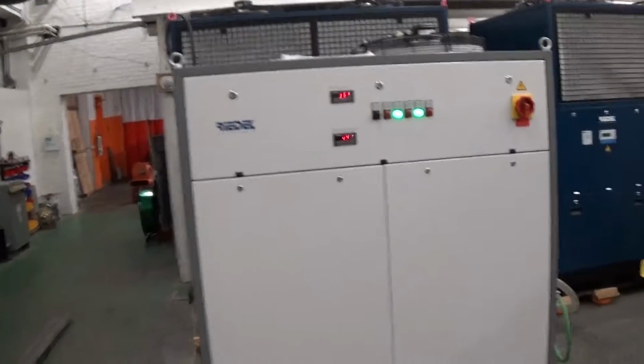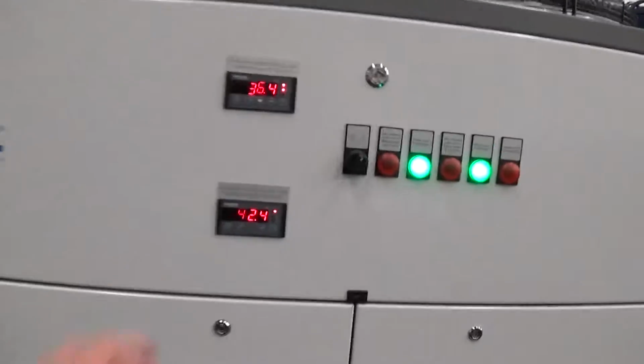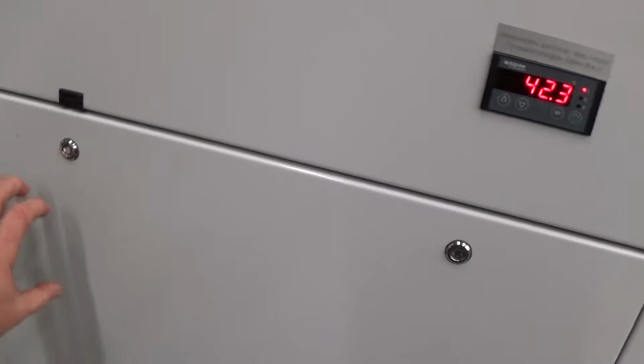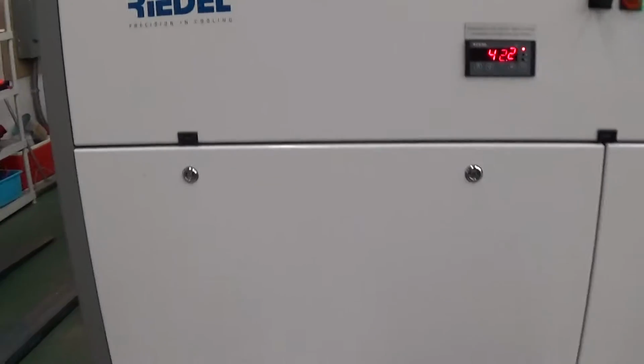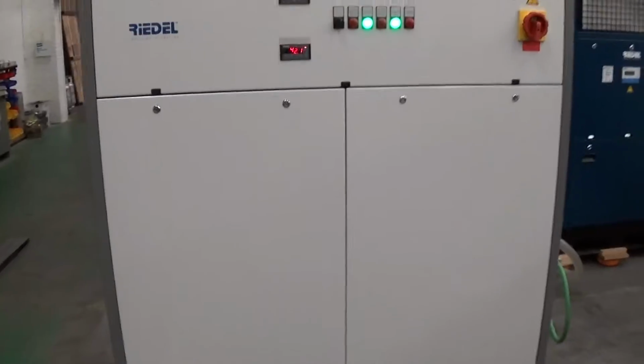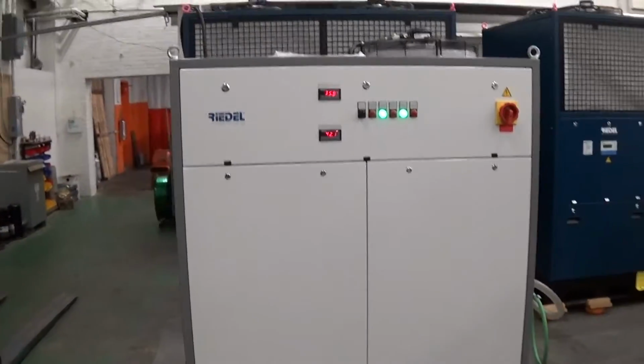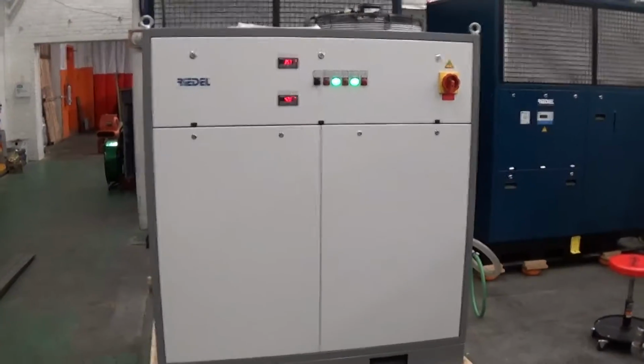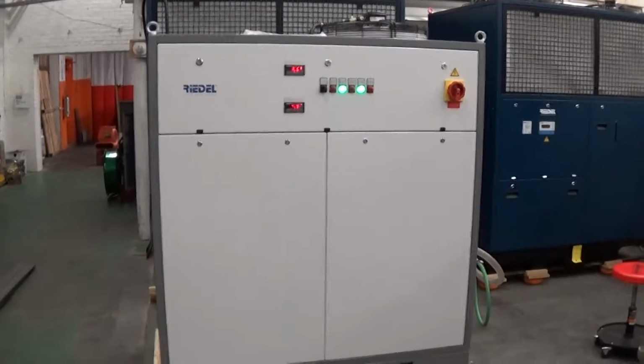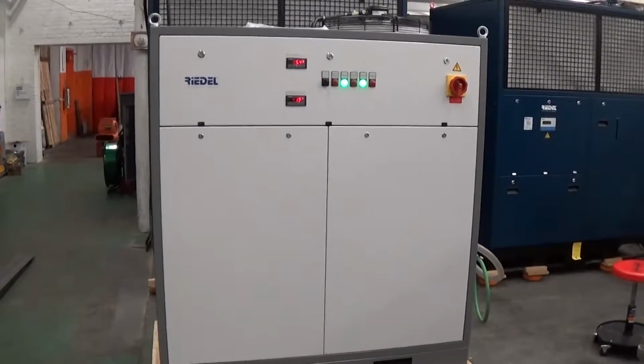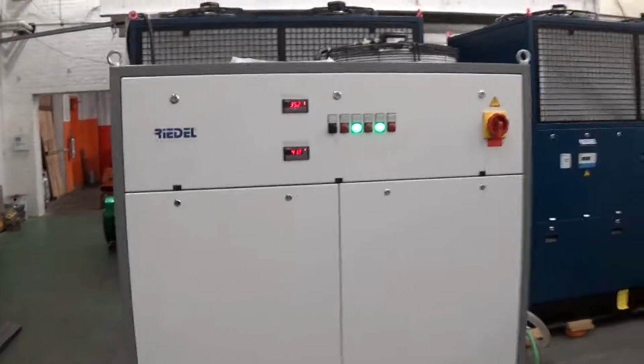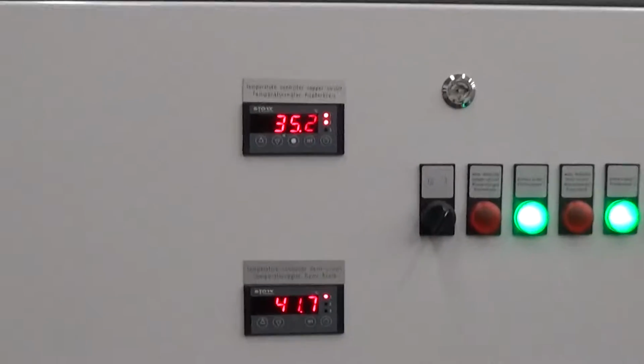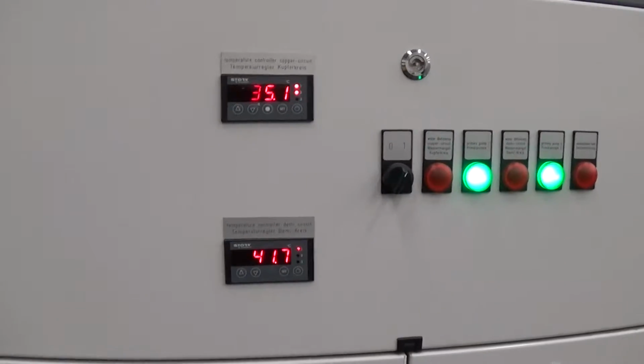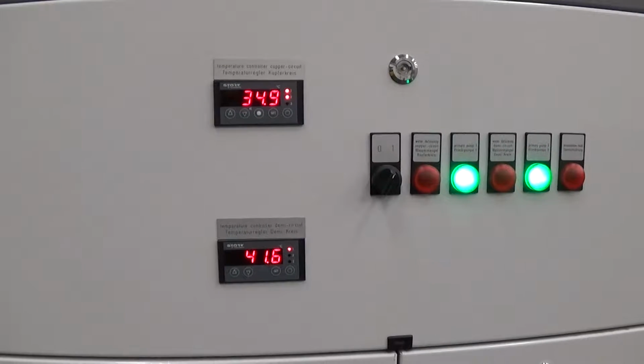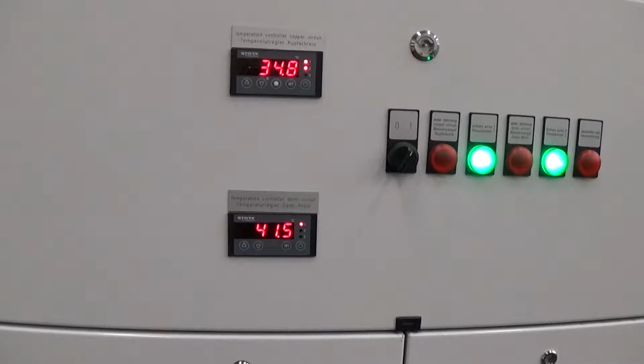What that basically meant is you heard a click. This one turned off, and then one of the pressure switches here, you just press the reset button. And that's what should happen on one like this when you have the side covers off and you have slightly higher tank temperatures like I created for this test. So you can see we're starting to chill fairly rapidly here. The only load we have is the load in the tanks.